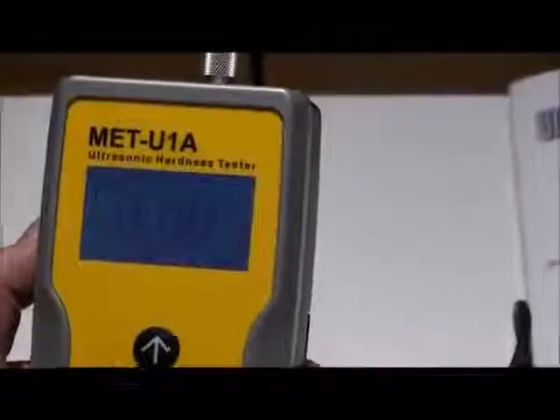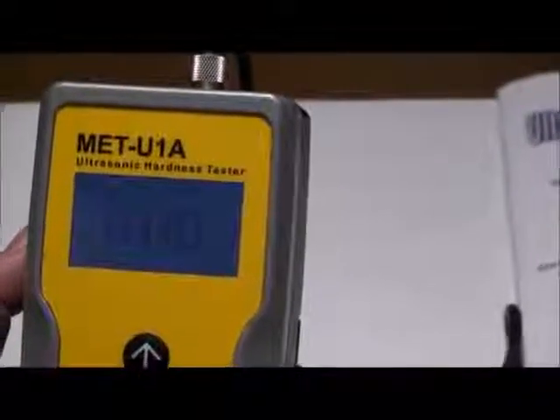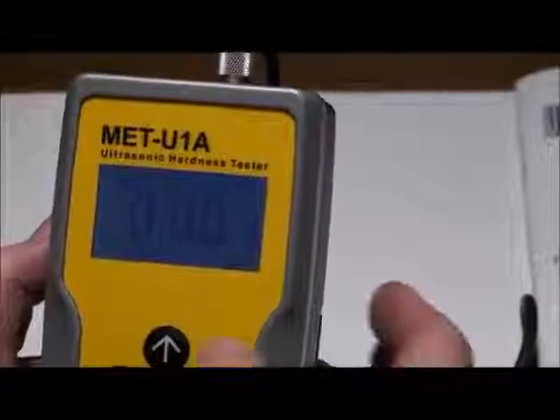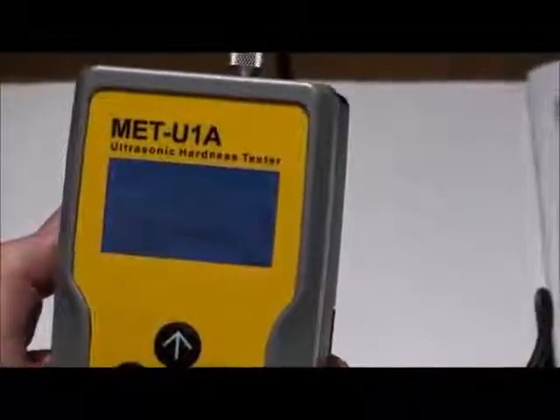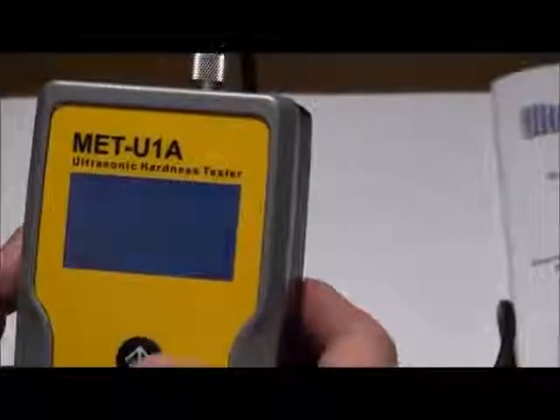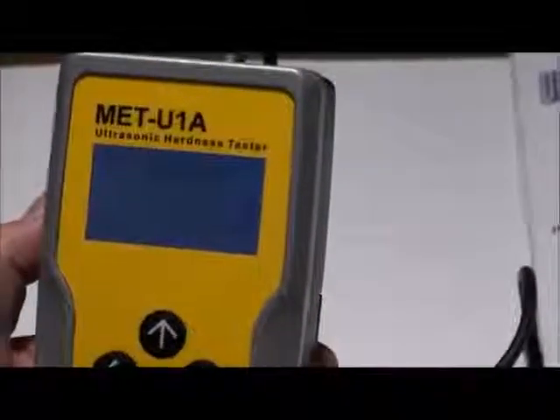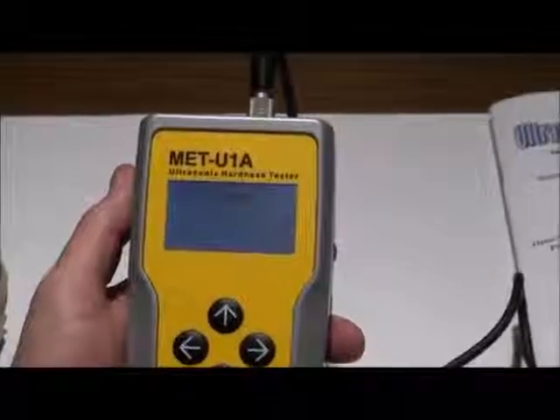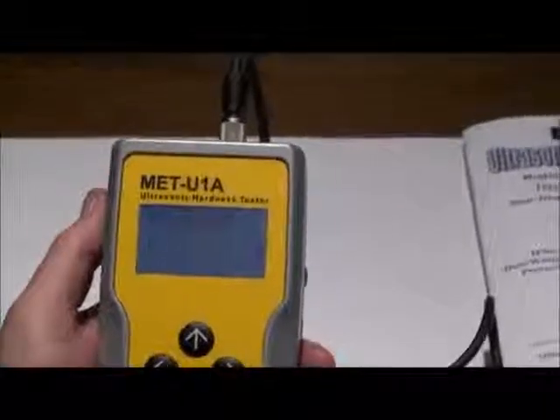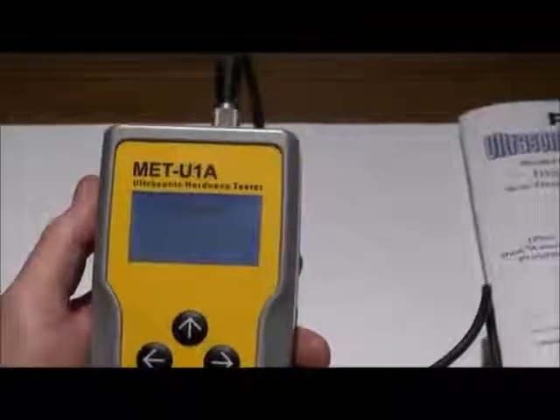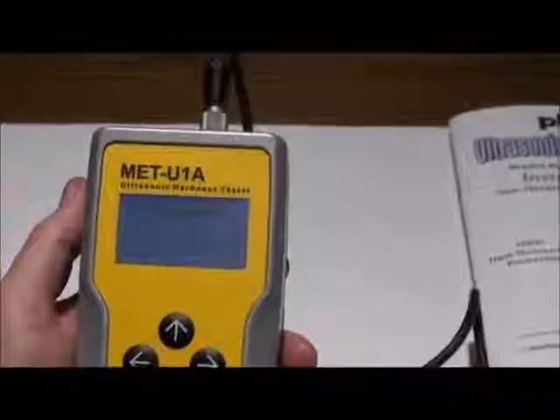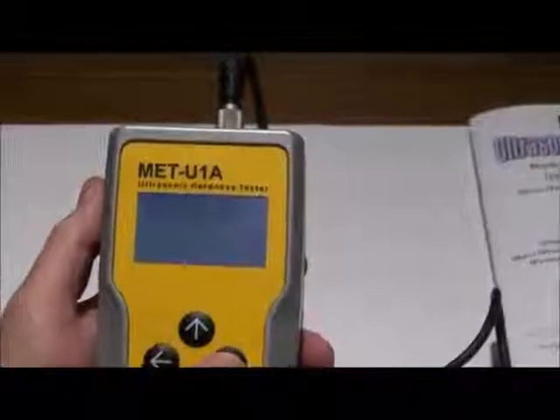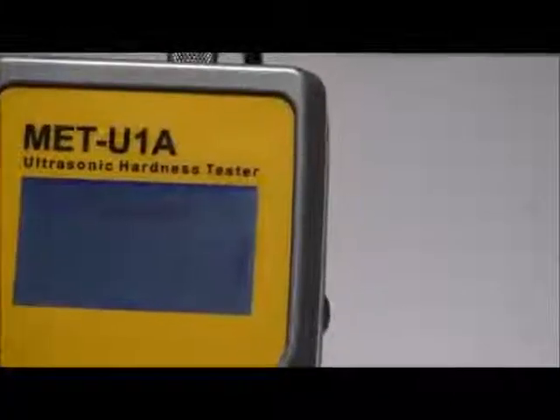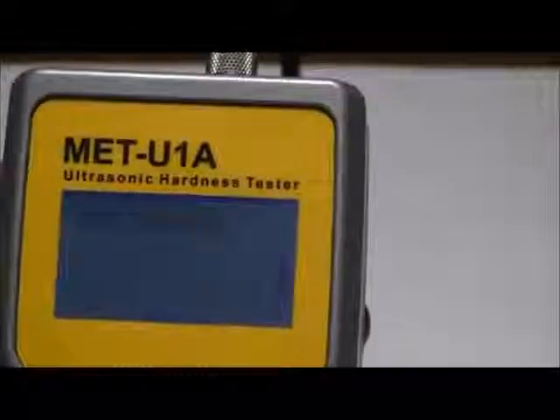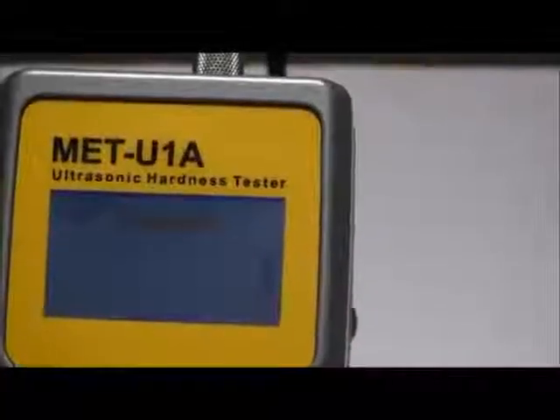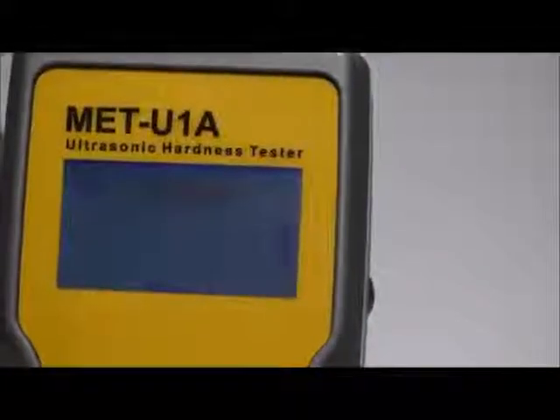The main interface screen brings you up in test mode, and from there it is easy to navigate throughout the menu. Hitting the up arrow button, you now see the word test flashing with arrows left and right. Hit the up arrow again, and this will bring us to scale. You will now see the word scale flashing with arrows. Left of this is the scale now being used, probably HRC, used for steels. If you press the right arrow button, you'll scroll through to HRB. This is used for aluminum. HV again is used for steel. HB, which is Brinell, is also used for steel.